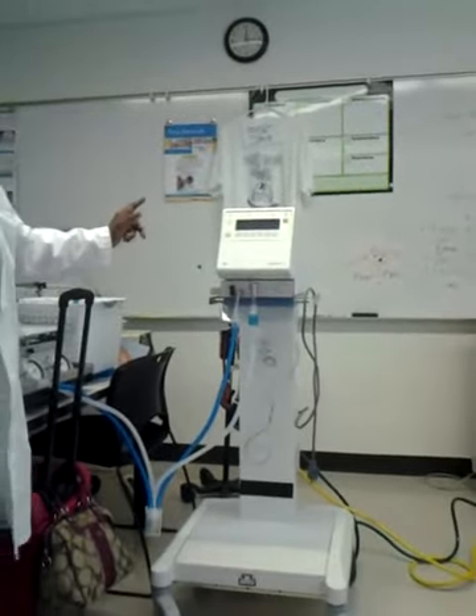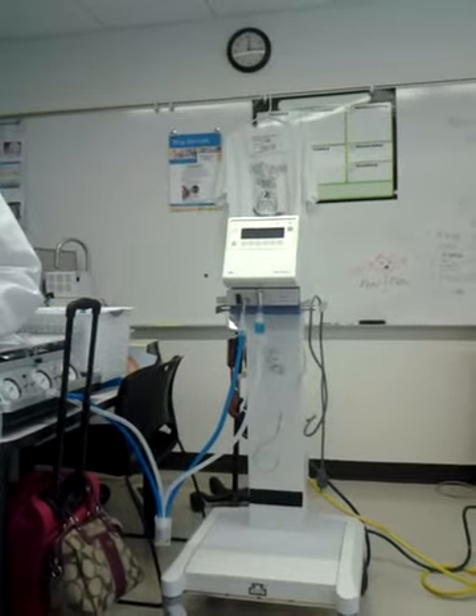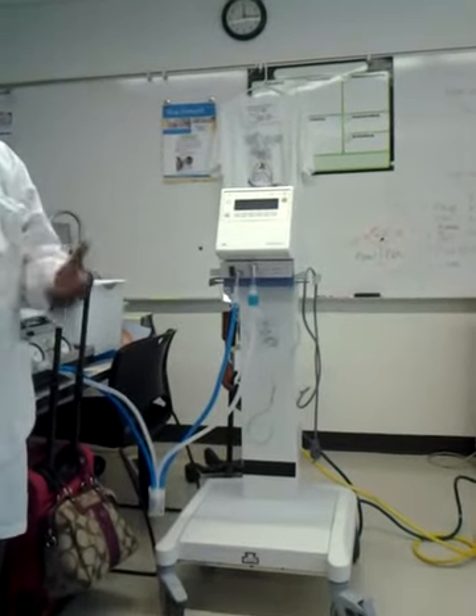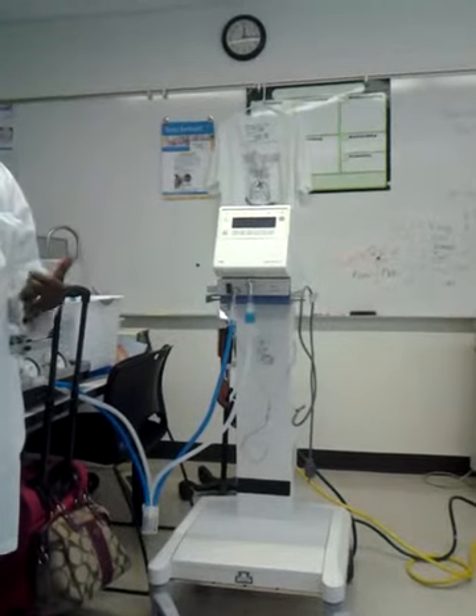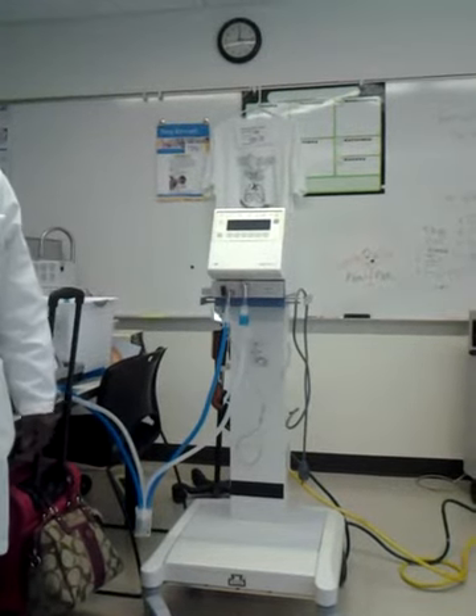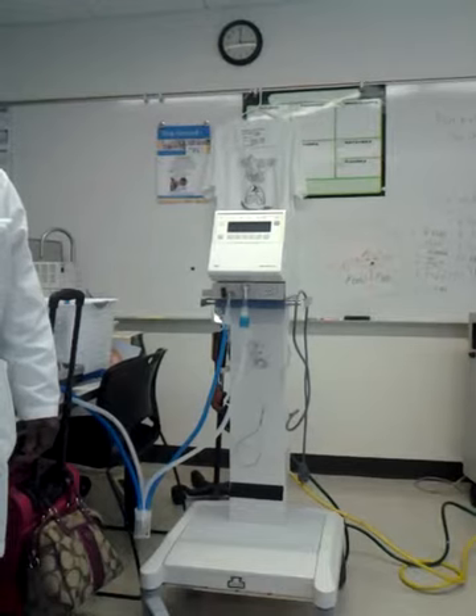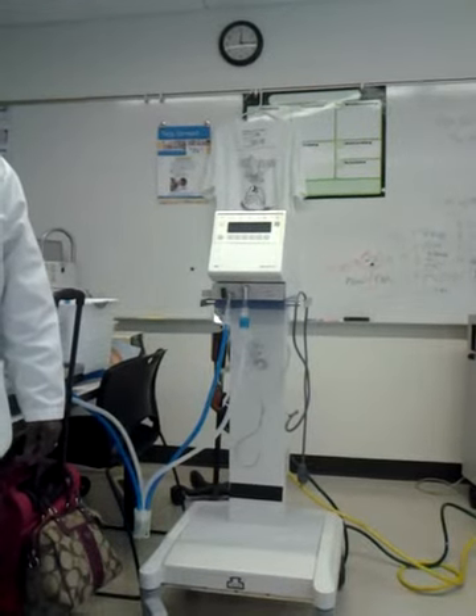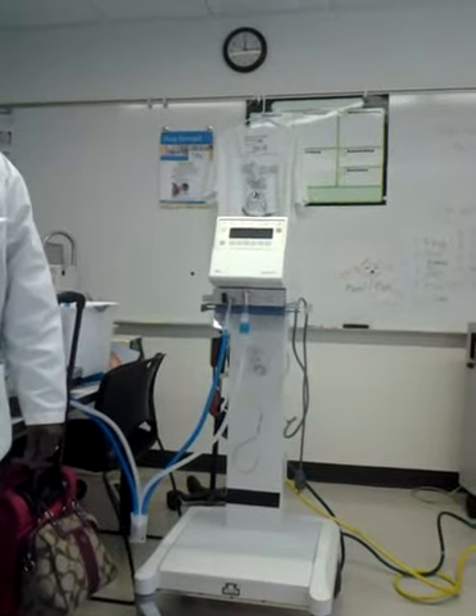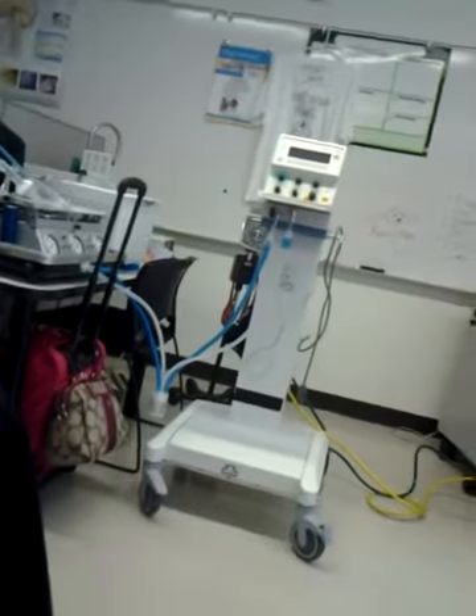Okay. So it's easier to ventilate them with pressure ventilation. We tried volume ventilation years ago, and they have been trying it again since then with your full-term or larger infants, or when you're in the pediatric community. But when you're working with the neonates, it's much easier to set a pressure, but you still have to make sure you're giving sufficient volume to adequately ventilate them. This particular machine has to have 50 psi air and oxygen going through, and I have to turn on this loud thing.